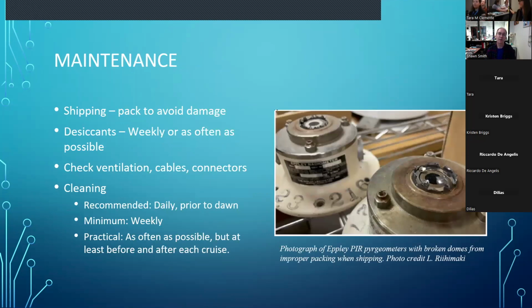For maintenance, one of the biggest issues—shown in this photo—is pyrgeometers that weren't well packed during shipping, resulting in broken domes. How radiometers are packed and shipped is one of the top causes of damage. Many of these radiometers have desiccants; some you can change yourself depending on the manufacturer. The recommendation is to check them and potentially change them weekly, or as often as possible, since moisture can really affect the measurements.